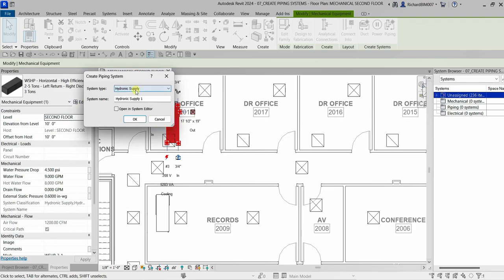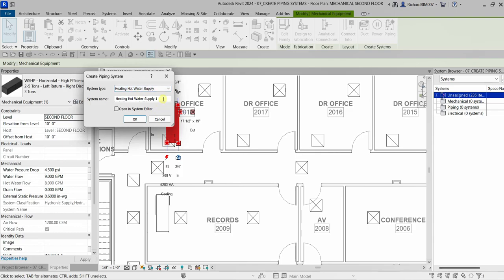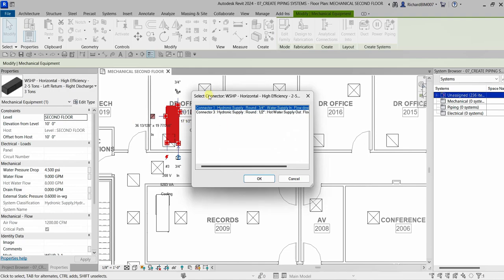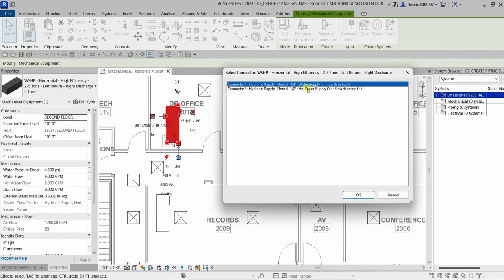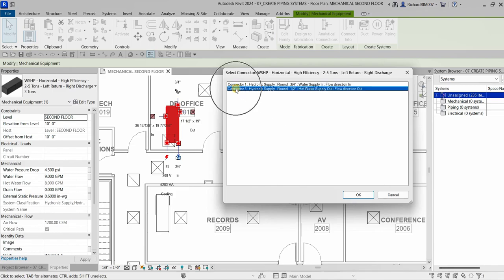Clicking the dropdown arrow shows several system type options based on the connectors in the family. I'll select the one I created — Heating Hot Water Supply — and change the name to 'Hot Water Supply - 1.' I'll turn on the system editor and select OK. I now have two connectors with hydronic supply: one is water supply, flow direction in, and the other is hot supply out, flow direction out. I'll select connector number three — the hot water supply out.